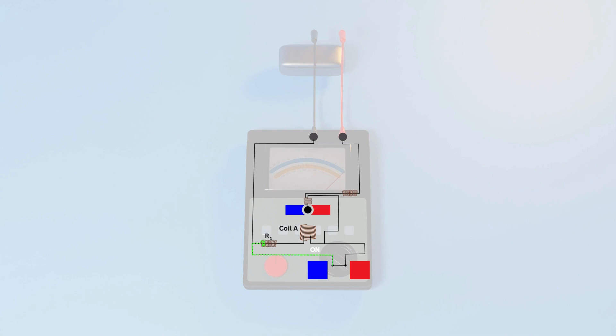When the Megger is switched on, a voltage is generated which is applied across the voltage coil A through a resistance R1. When the terminals X and Y are free initially, no current flows through coil B. The torque produced by coil A rotates the moving element to show infinity.